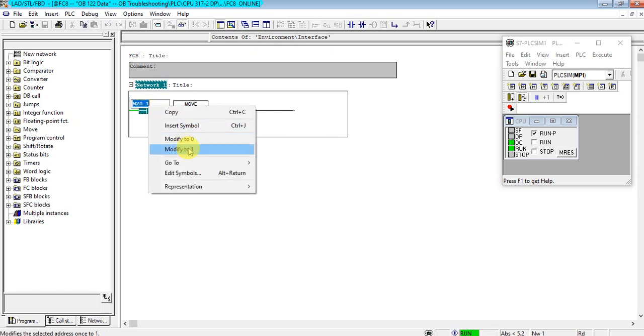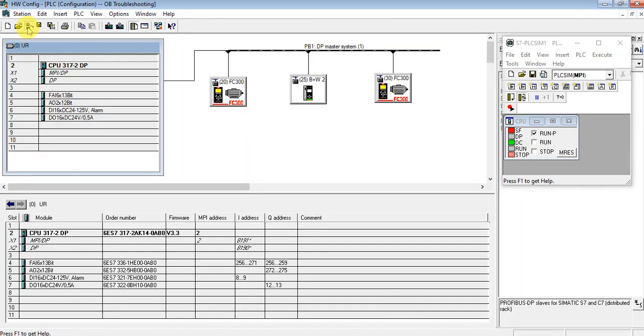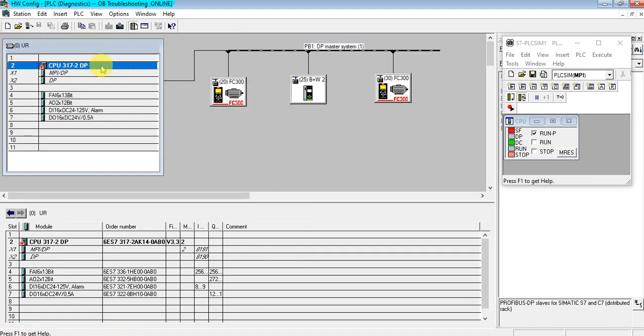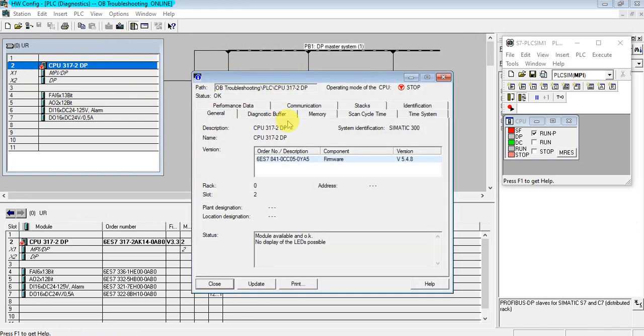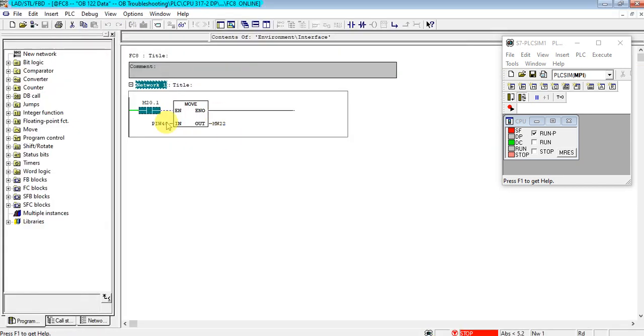Let's enable this one. As you see, the CPU goes to stop mode. Let's see the error on our diagnostic buffer. The CPU stopped due to an IO access error. OB122 is not loaded because input address 40 is not added in my hardware configuration.